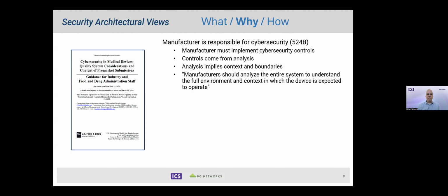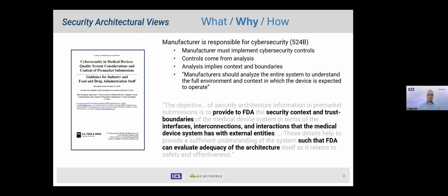So the quote from the guidance is, the manufacturer should analyze the entire system to understand the full environment and context in which the device is expected to operate. Another section that I'll paraphrase is that the FDA wants the submission to provide security context and trust boundaries, interfaces, interconnections, and interactions that the medical device has with external entities, such that the FDA can evaluate the adequacy of the architecture.